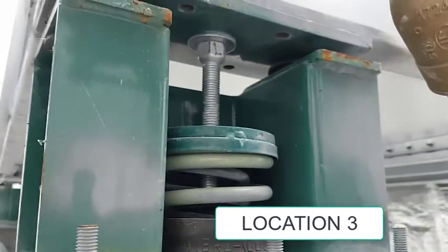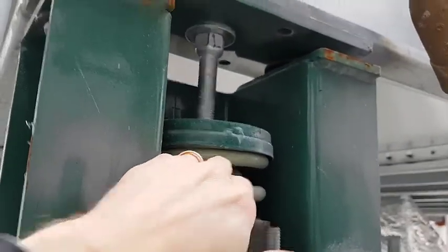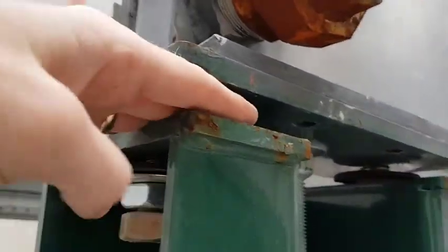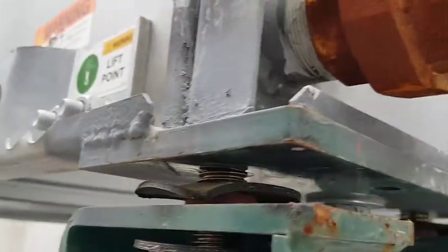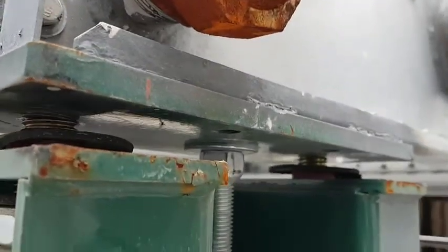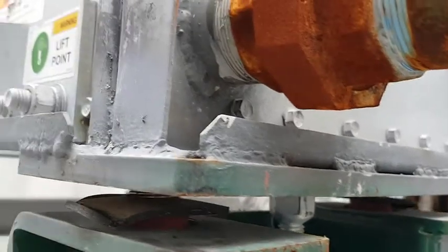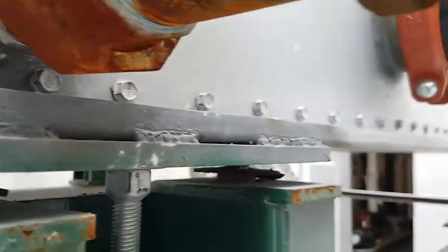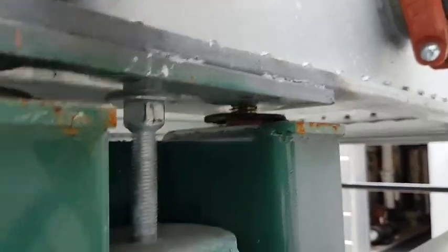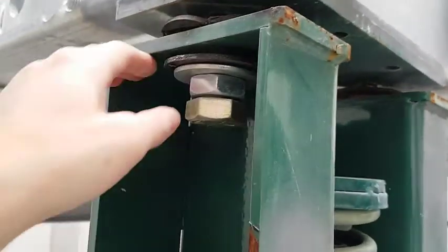The spring has been adjusted, and I can feel vibrations in the spring coils. There's more of a gap than necessary under the top plate. Although the snubber washer appears damaged, it's still able to do its job of minimizing metal-to-metal contact. The tower is attached to the isolator with welds that look okay. The hold-down nut and washer are free to move, and therefore not short-circuiting the isolation.